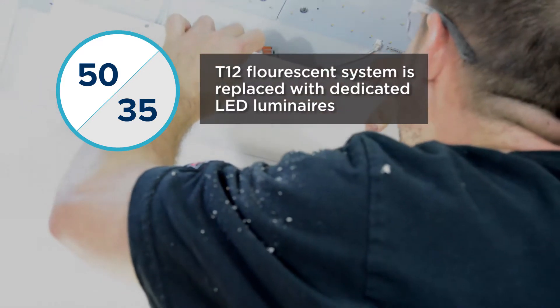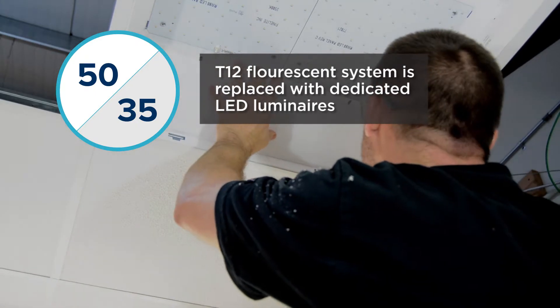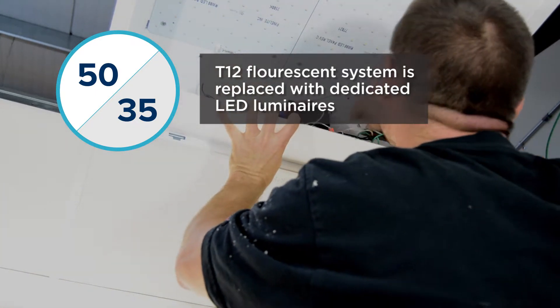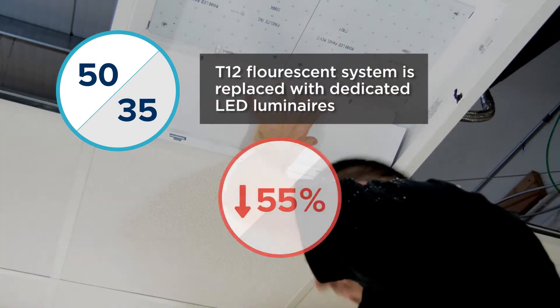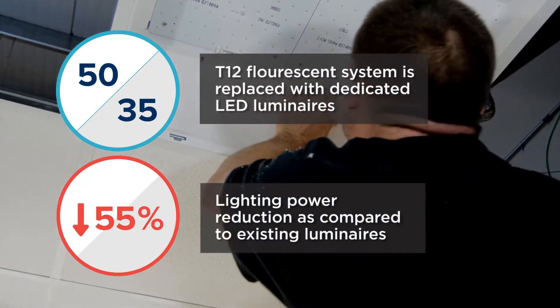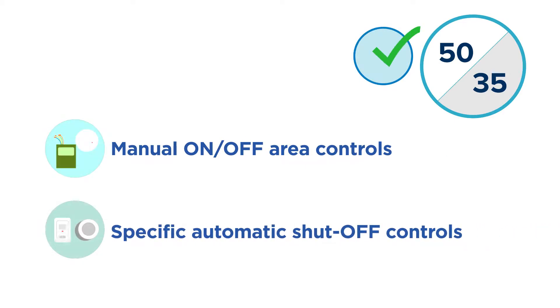Now let's look at an example of an entire luminaire alteration project that can use this compliance path. A retail business owner replaces all the existing T12 fluorescent troffers on the main sales floor with dedicated LED luminaires, thereby reducing the rated power of installed luminaires by 55%. This project meets the criteria of the new power reduction compliance path, assuming that the retrofit complied with the necessary manual on-off control and automatic shutoff control requirements. For this compliance path, the existing luminaire power must be documented to verify that the replaced or modified luminaires achieve the specified power reduction.